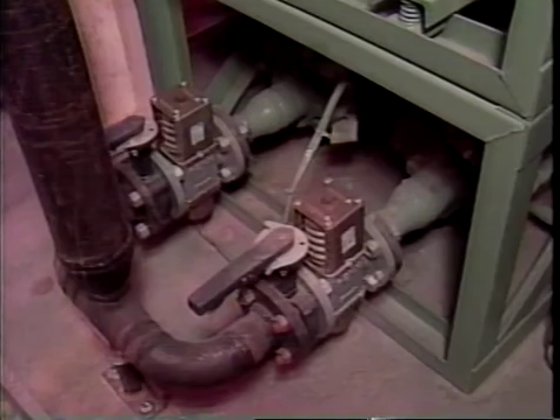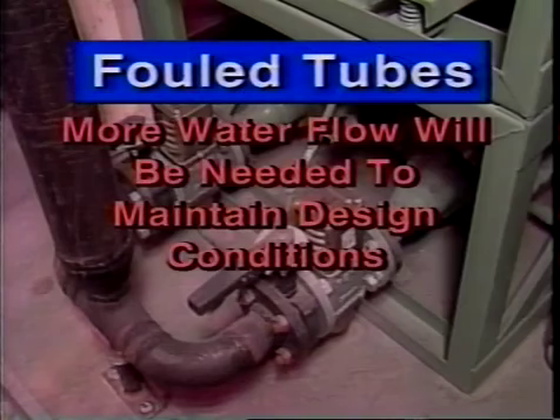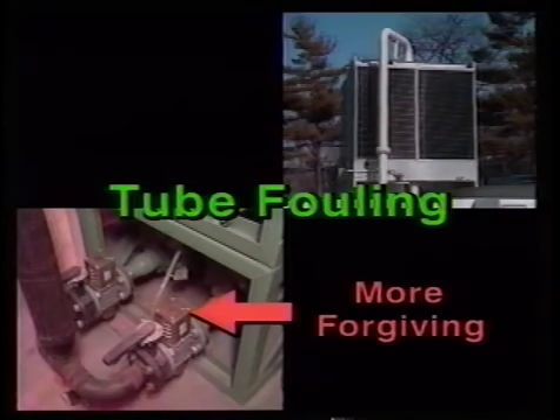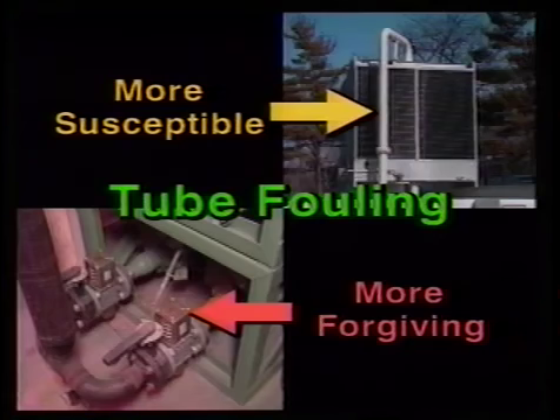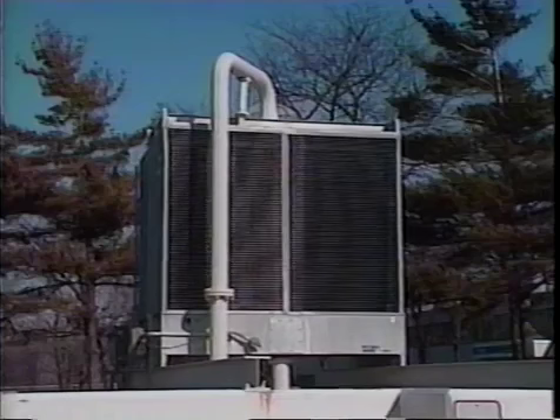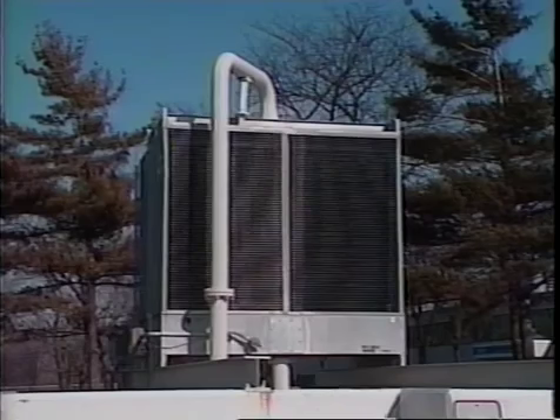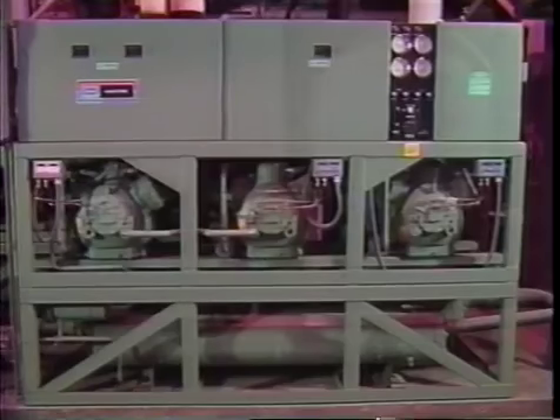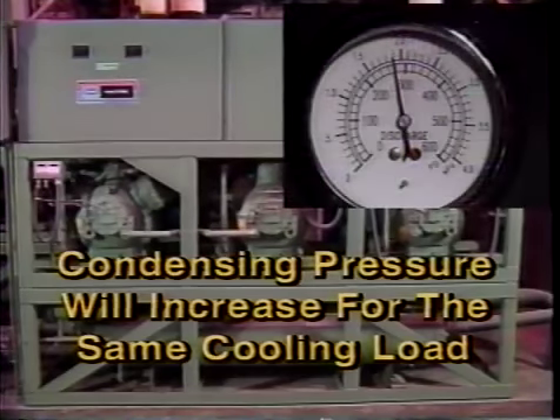An indication that the condenser tubes are getting fouled on a once-through system using a water-regulating valve to control condensing pressure is that over a period of time, more and more water flow will be needed to maintain design conditions. Once-through systems are more forgiving on fouling condenser tubes, while cooling tower systems are more susceptible to fouling. An indication that the tubes are getting fouled on cooling tower systems is that over a period of time, the condensing pressure will increase for the same cooling load.